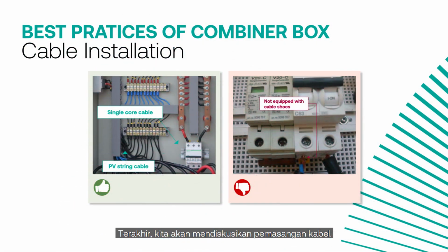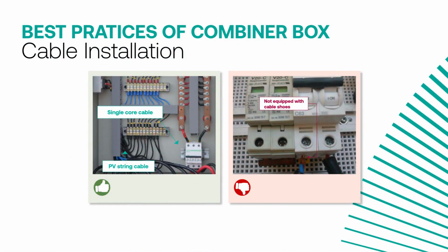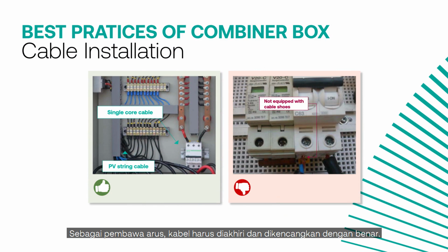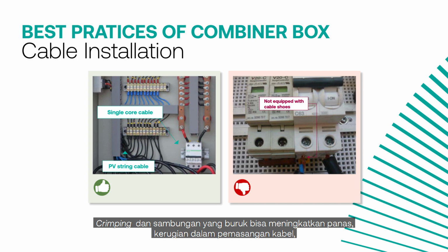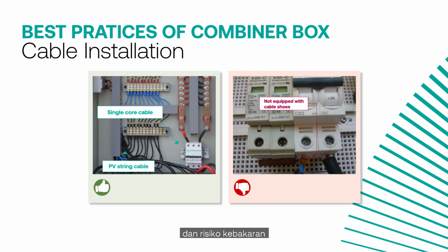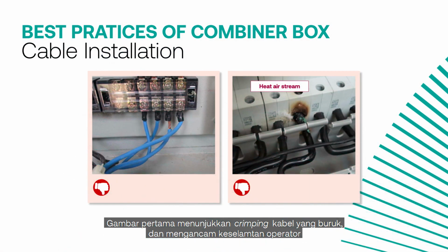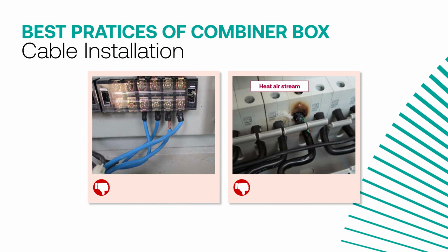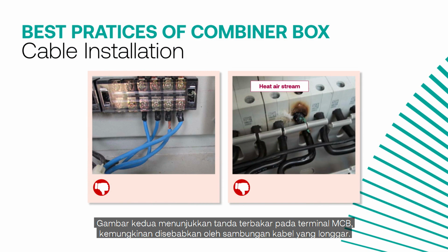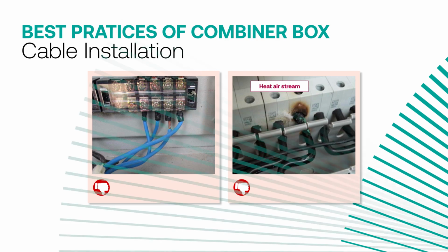Lastly, we are going to discuss cable installation. As the current carrying conductor, cables must be properly terminated and fastened. Bad crimping and connection can lead to increased heating, losses in wiring, and possible risk of fire. The first picture shows poor cable crimping that may risk the safety of the operator and lead to a ground fault. The second picture shows a burn sign at the terminal of the MCB, possibly due to an electric arc caused by a loose cable connection.